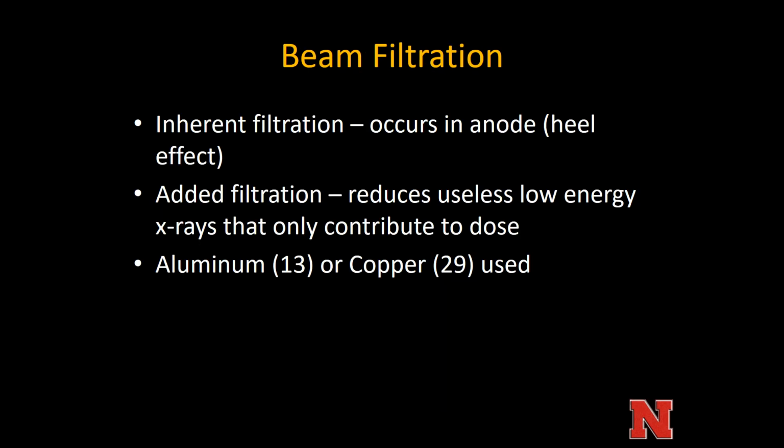All right, beam filtration. Inherent filtration occurs in the anode. The heel effect causes that. Additionally, we add filtration to reduce useless low energy X-rays that really only contribute to patient dose. Usually we're going to be using what I think of as soft metals like aluminum, which is number 13 on the periodic table of elements, or copper, which is 29. So, softer, lower density or lower weight metals.